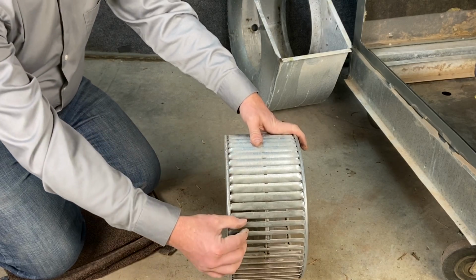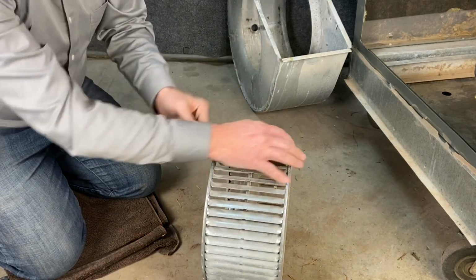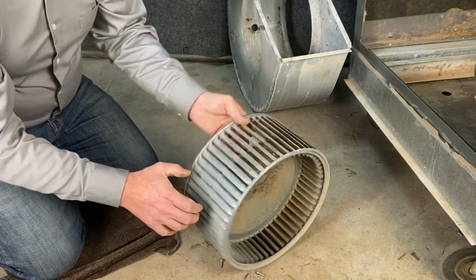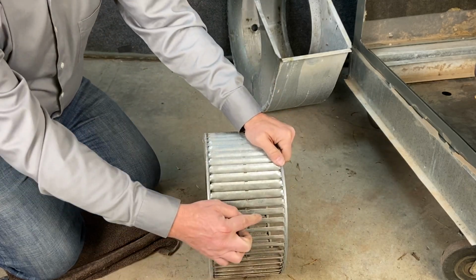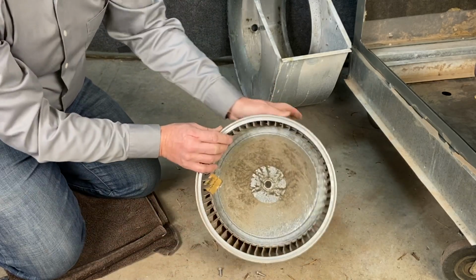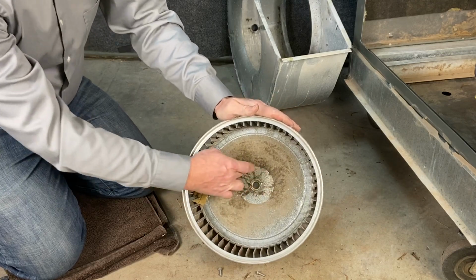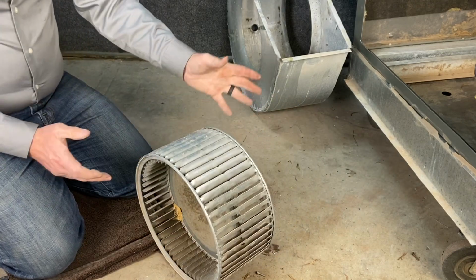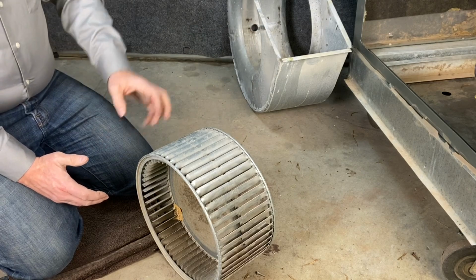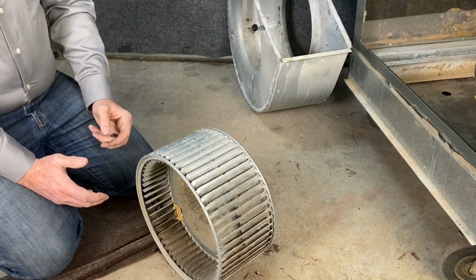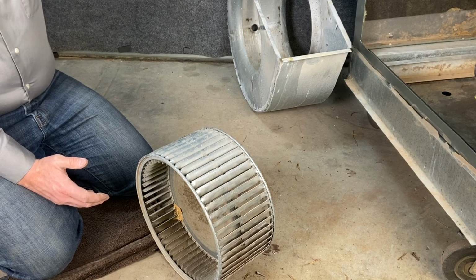But here we can see that there's a lot of dirt inside of these fins. I don't know if it's going to show up on the camera or not, but each one of these is just really, really dirty. All of this needs to be cleaned out. So that's the basics of our blower side. We're going to go ahead and go through the rest of that operation. We're going to start with the burner, and we're going to cover some of those topics next.